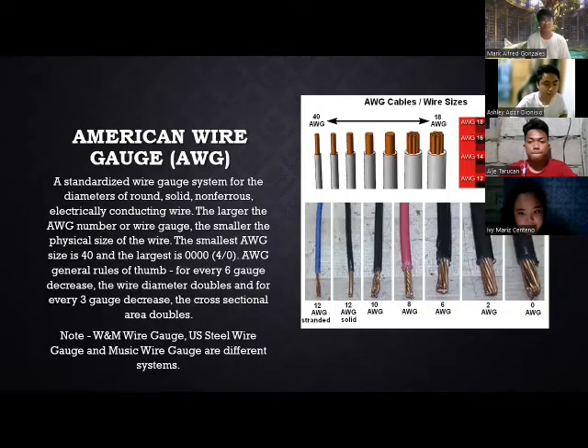Next naman dito ay ang American Wire Gauge or AWG. The AWG is a standardized wire gauge system for the diameters of round, solid, non-ferrous, electrically conducting wire. The larger the AWG number or wire gauge, the smaller the physical size of the wire. The smallest AWG size is 40 and the largest is 0000 or 4/0. AWG general rule of thumb is for every 6 gauge decrease, the wire diameter doubles, and for every 3 gauge decrease, the cross-sectional area doubles.